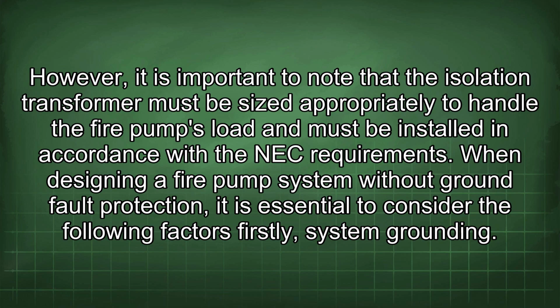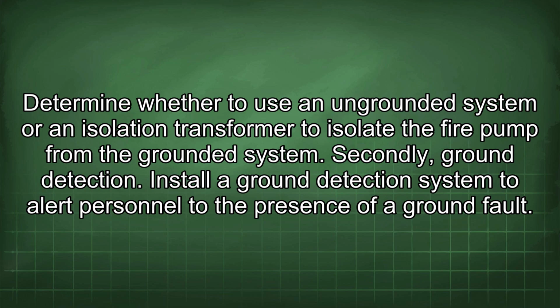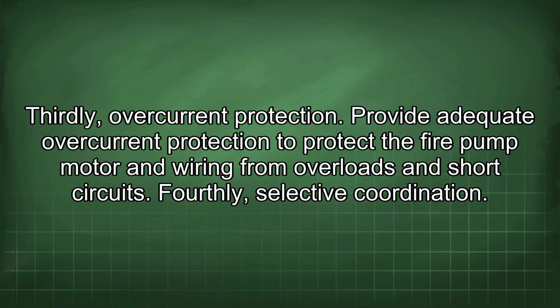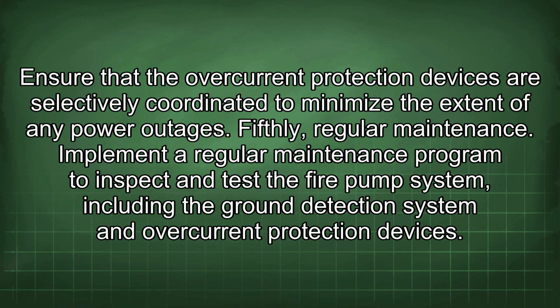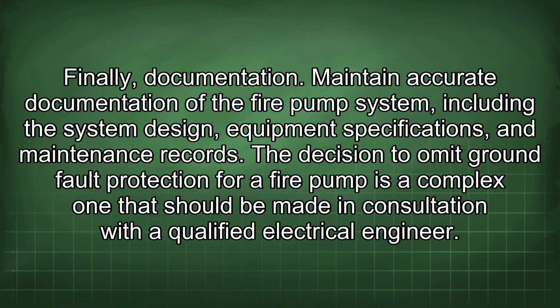When designing a fire pump system without ground fault protection, it is essential to consider the following factors. Firstly, system grounding. Determine whether to use an ungrounded system or an isolation transformer to isolate the fire pump from the grounded system. Secondly, ground detection. Install a ground detection system to alert personnel to the presence of a ground fault. Thirdly, overcurrent protection. Provide adequate overcurrent protection to protect the fire pump motor and wiring from overloads and short circuits. Fourthly, selective coordination. Ensure that the overcurrent protection devices are selectively coordinated to minimize the extent of any power outages. Fifthly, regular maintenance. Implement a regular maintenance program to inspect and test the fire pump system, including the ground detection system and overcurrent protection devices. Finally, documentation. Maintain accurate documentation of the fire pump system, including the system design, equipment specifications, and maintenance records.